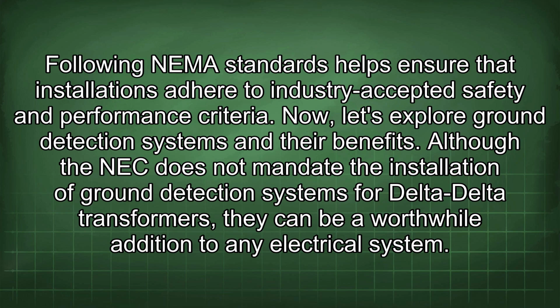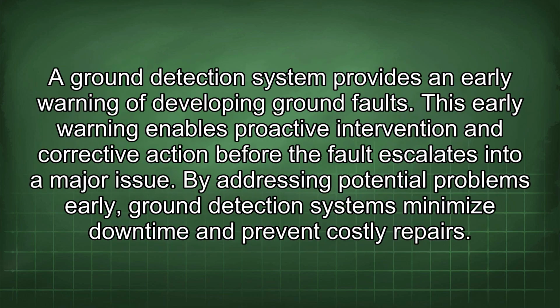Although the NEC does not mandate the installation of ground detection systems for delta-delta transformers, they can be a worthwhile addition to any electrical system. A ground detection system provides an early warning of developing ground faults. This early warning enables proactive intervention and corrective action before the fault escalates into a major issue. By addressing potential problems early, ground detection systems minimize downtime and prevent costly repairs.